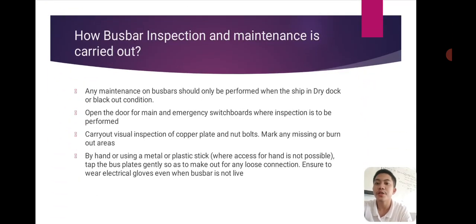How bus bar inspection and maintenance is carried out. Any maintenance on bus bars should only be performed when the ship is in dry dock or blackout condition. Open the door for the main and emergency switchboards where inspection needs to be performed. Carry out visual inspection of copper plates and nut bolts. Mark any missing or burned out areas by hand, or using a metal or plastic stick where access by hand is not possible. Tap the bus plates gently so as to make out any loose connection. Ensure to wear electric gloves even when the bus bar is not live.